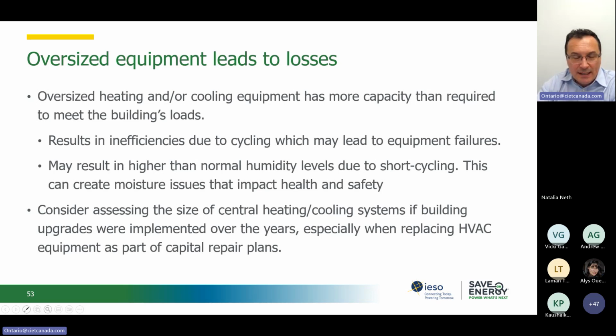I've seen many reports done in existing buildings where the chiller plant is operated at 60% capacity on the warmest day of the year. What does this mean? It means that that chiller is actually having 40% capacity that's not utilized, and maybe on that very warm day, it's not a big deal. It's actually good to have a little bit of spare capacity, but for many of the other days when we don't need that much cooling, the chiller is going to operate less efficiently, and sometimes even creating problems for servicing the chiller because of that capacity. So cycling this on and off can cause problems, and it is due to the higher capacity than required.